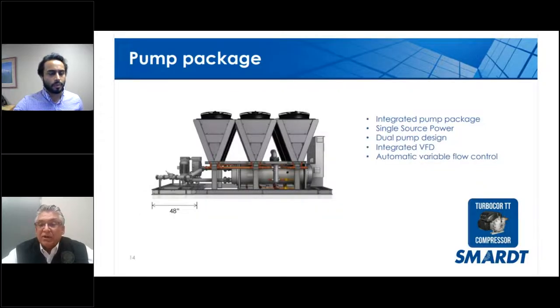In addition to that, we can provide integrated pump packages. So you have a single point connection, with the chiller and the pump already installed as an assembly. It also works very well on variable primary flow in those applications. We use Armstrong pumps with our system control algorithms. So also dual pump design, single pump or dual pump, for redundancy and for lead lag.